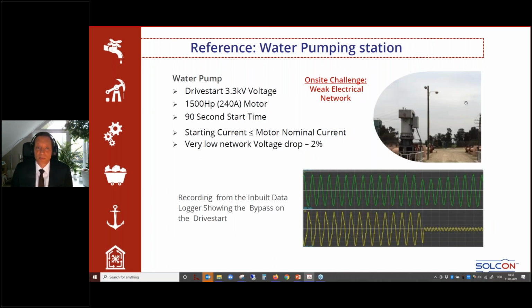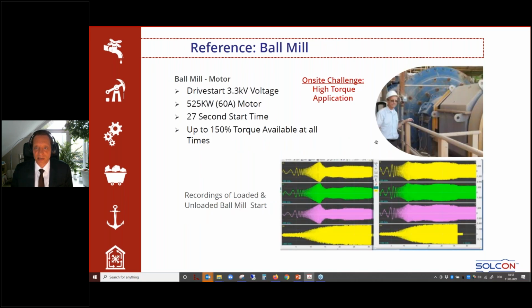Water pumping station: we needed a very low starting current in order to protect the network. The requirement was that the voltage drop needed to be less than 2%. And we had a very long starting time with this. This is an application in Israel, which I have seen personally, and it is working very well. You see here the current for the motor, and here you see the current of the inverter, smooth transition and working to the fullest satisfaction of the customer.